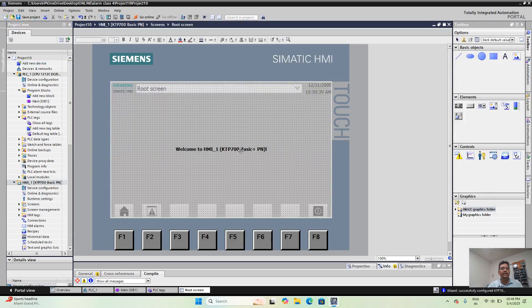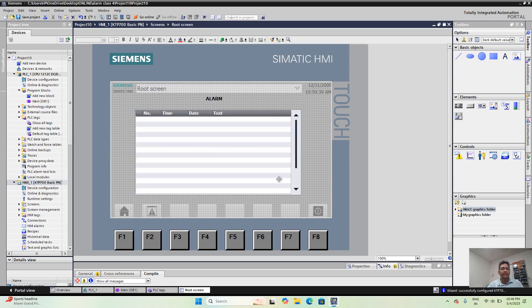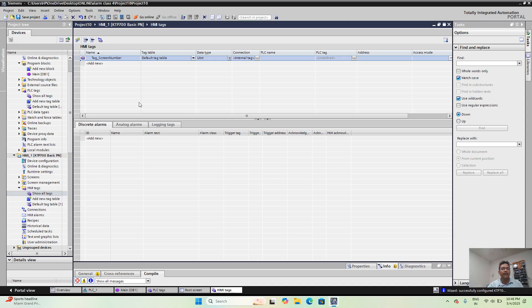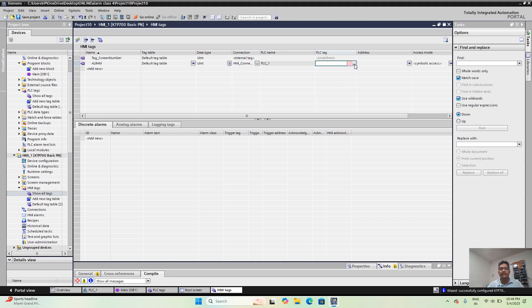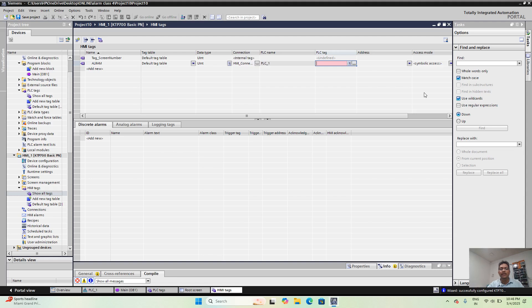Now the base screen, home screen, or root screen is created. You can erase the welcome note or edit it as per your requirement. I am typing 'alarm' here. Then in the input control you can see the alarm control — just drag and drop it here. Then, just as you gave the PLC tag, similarly you have to mention the HMI tag. I have typed the alarm tag and mentioned the HMI connection with the same address as the integer MW20 alarm.